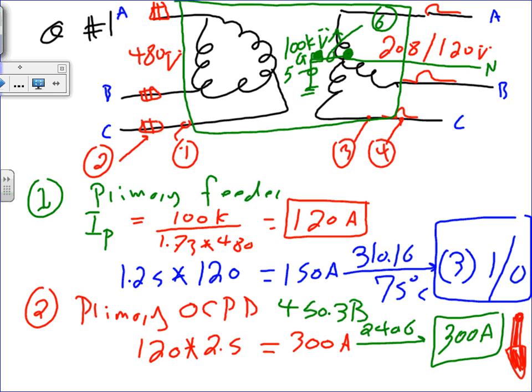This neutral will be the neutral for the 208/120, and there might be another neutral there for the 480/277 that might be in the building, which almost always there will be two neutrals. One for the 277 and one for the 120, and we do not tie these two neutrals together. We keep them separated. That's why it's a separately derived system. You created your own new neutral. And I can create as many neutrals as I want, as long as I go delta-Y, and bond neutral to ground again. Every time you create a neutral, you have to bond.